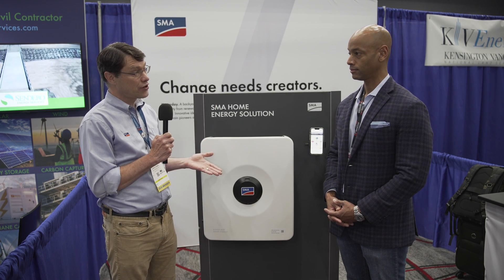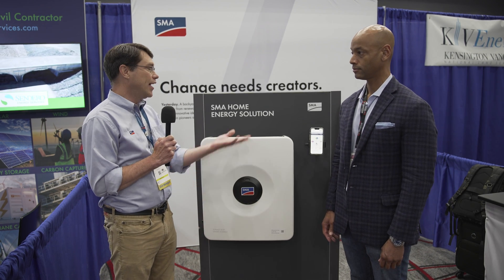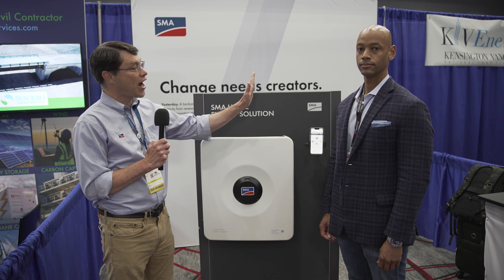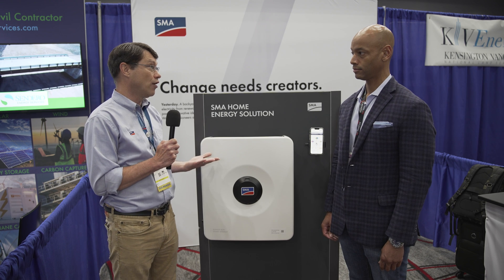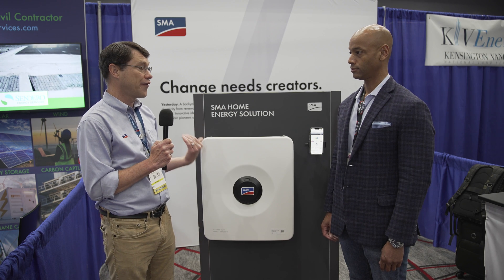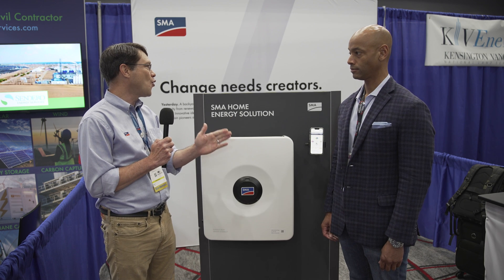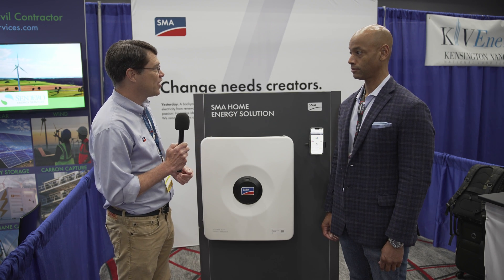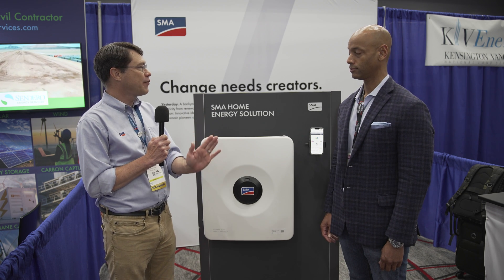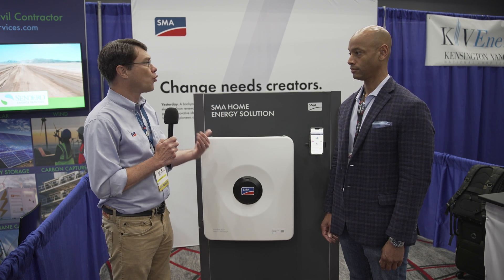That's our first stage of backup. A second stage will be what we call Backup Select — a physical box accessory that will look very much like the Sunny Boy Smart Energy but be below it. On installation, an installer can work with the homeowner to figure out up to six single-phase circuits they want normally grid-powered but that can be powered by this system should the grid fail. That is a full microgrid interface device that will do automatic switching of grid power to those circuits over to the inverter should the grid fail. We're also partnering with SPAN, the smart panel manufacturer, for more of a full home backup — customers in Texas may want to run air conditioning should the power go out, and that's a big load.